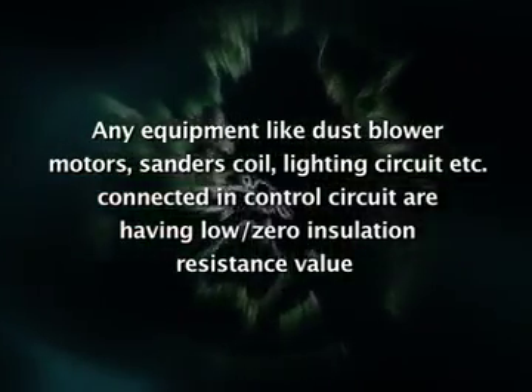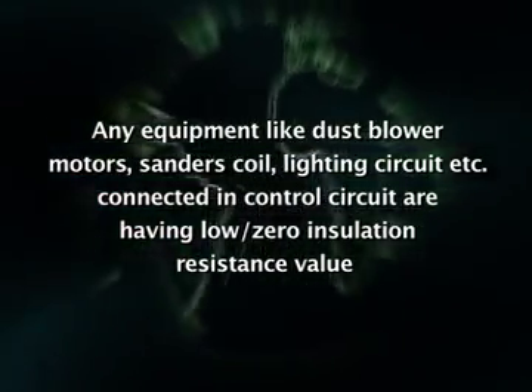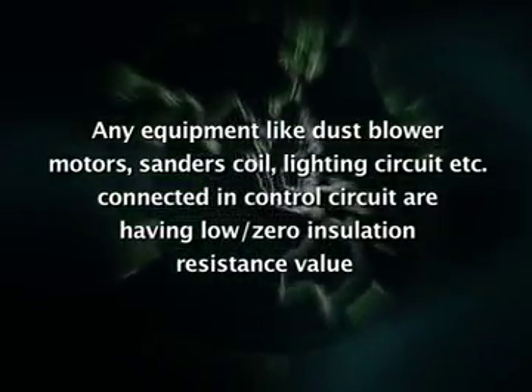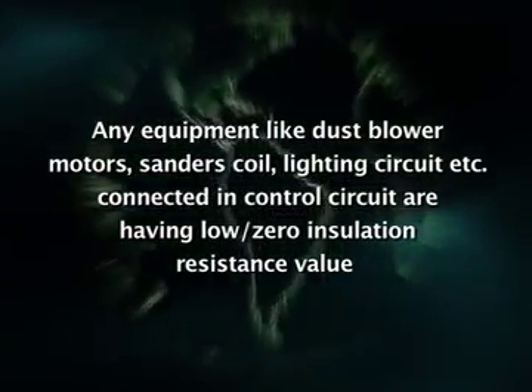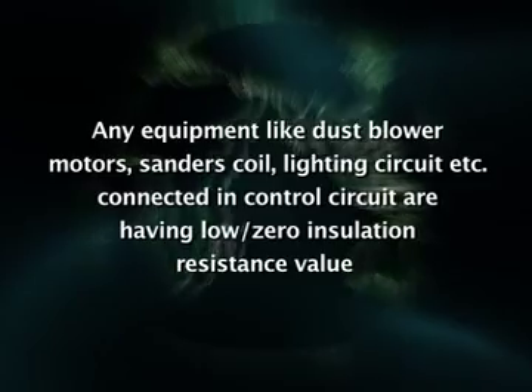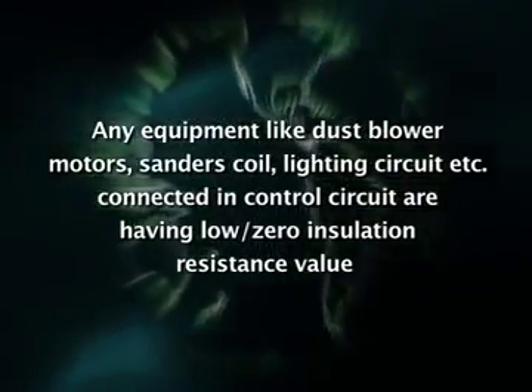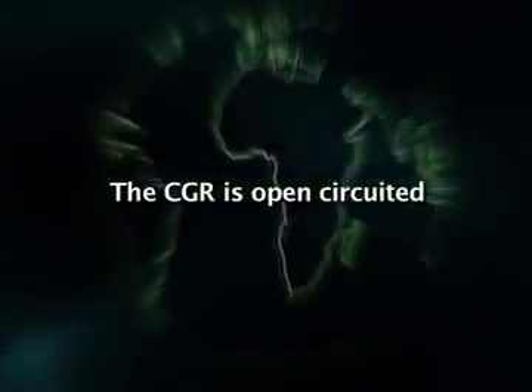Any equipment like dust blower motors, sanders, coil lighting circuit etc. connected in control circuit are having low or zero insulation resistance value. The CGR is open circuited.